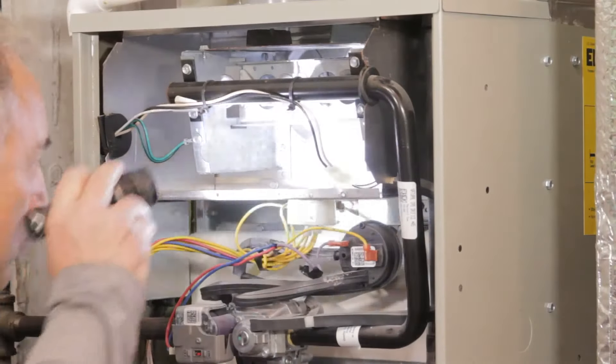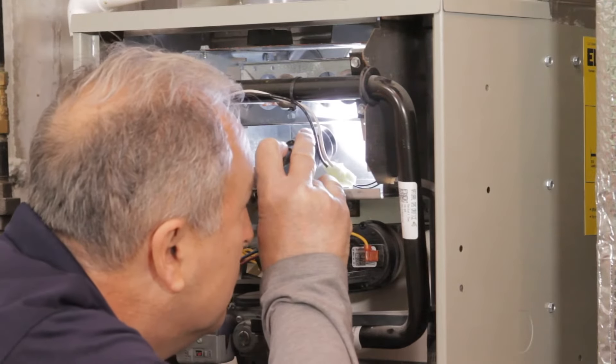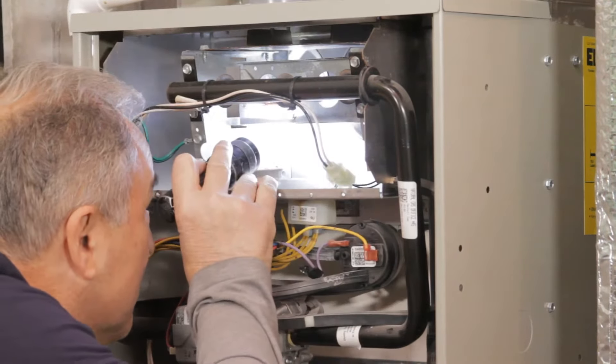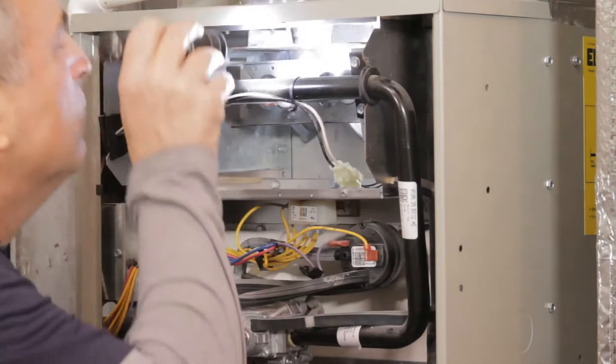Next, we check the heat exchanger for cracks and leaks. A cracked heat exchanger can be seriously dangerous. If there's a heat exchanger crack, it can cause carbon monoxide gas to leak out of your gas furnace.